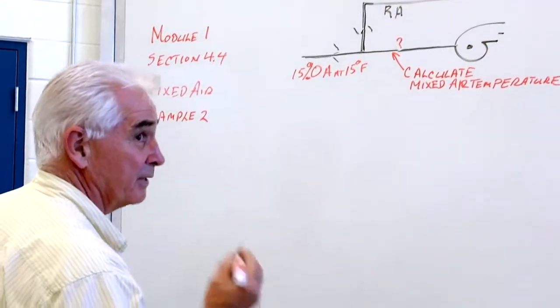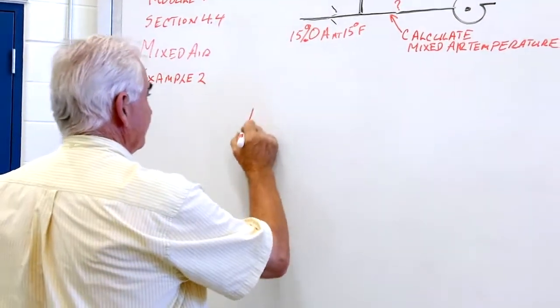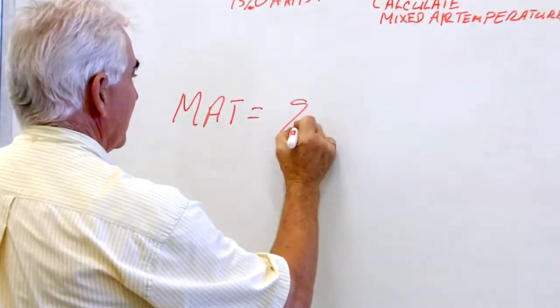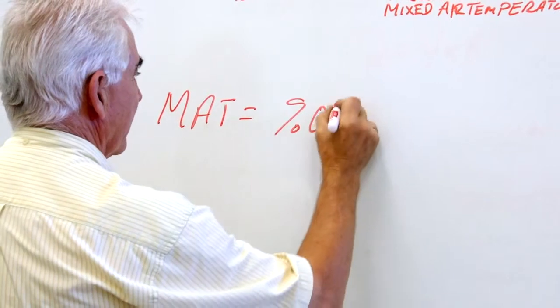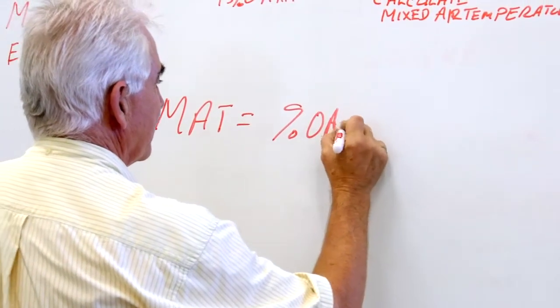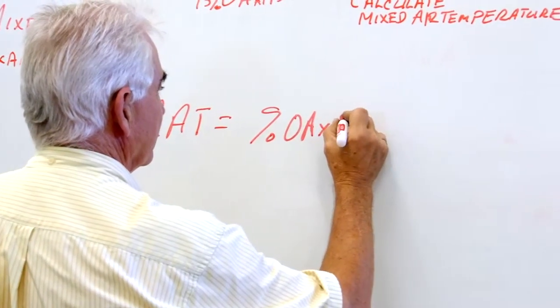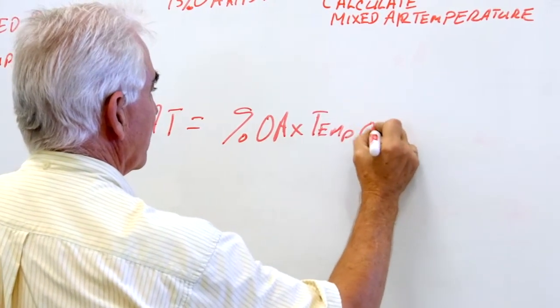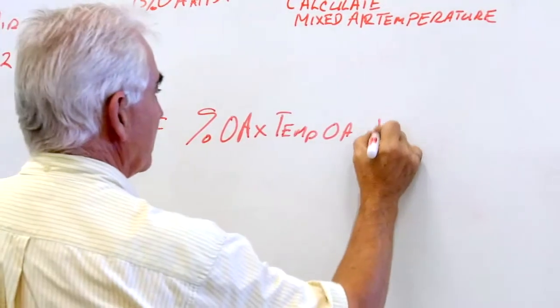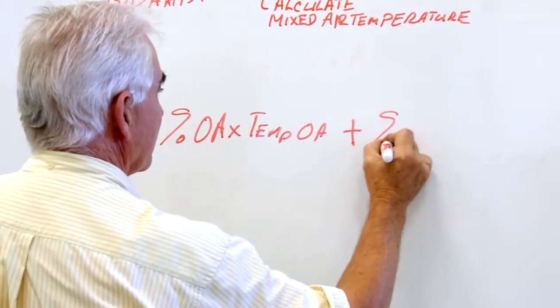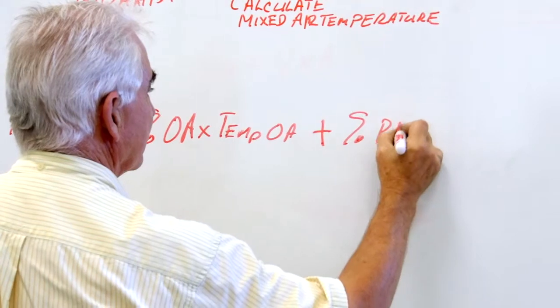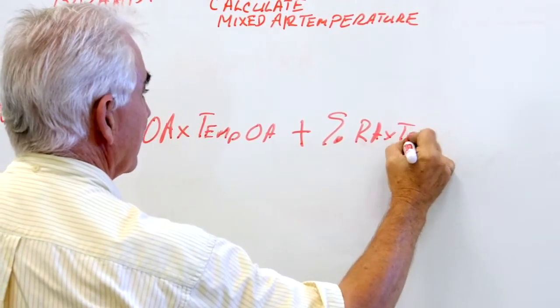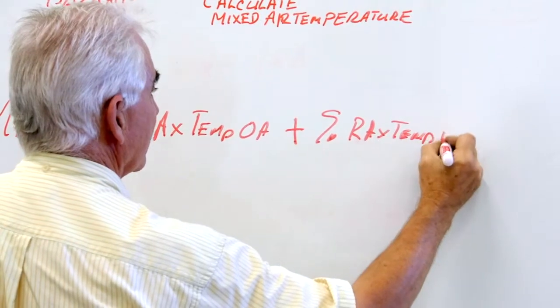Our equation for mixed air temperature is equal to the percent of outdoor air times the temperature of the outdoor air plus the percent of return air times the temperature of the return air.